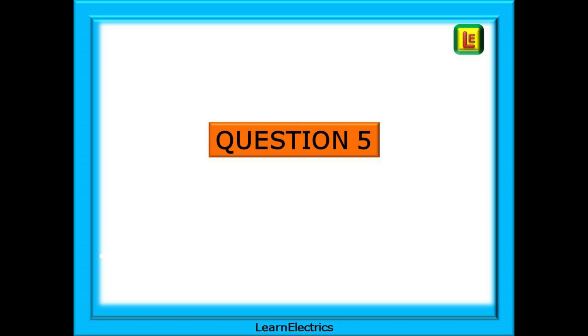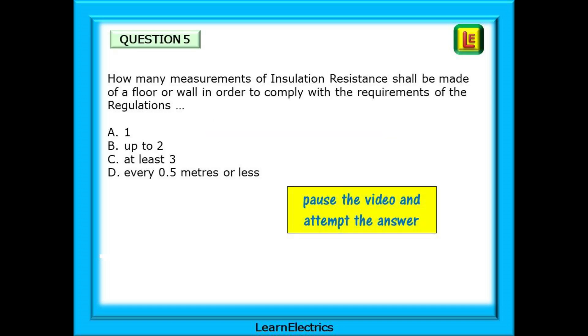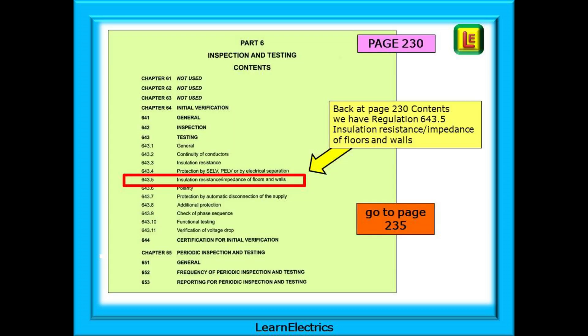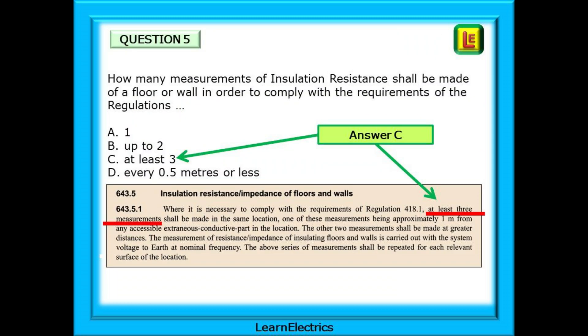Question 5: how many measurements of insulation resistance shall be made of a floor or wall in order to comply with the requirements of the regulations? Back to page 230, the contents page. There is Regulation 643.5 — Insulation Resistance and Impedance of Floors and Walls — just what the question is asking about. Go to page 235. Here is Regulation 643.5.1 and there is the answer: at least 3. Answer C.